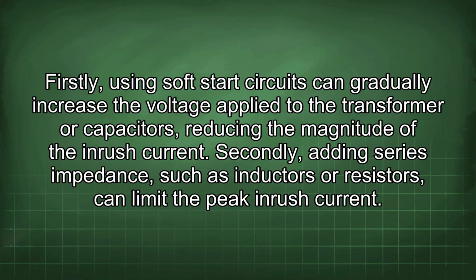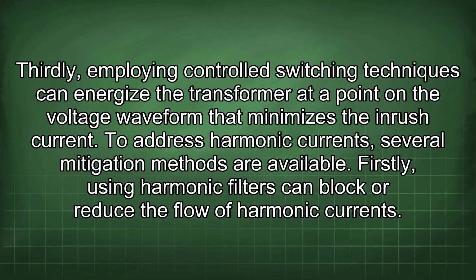Firstly, using soft-start circuits can gradually increase the voltage applied to the transformer or capacitors, reducing the magnitude of the inrush current. Secondly, adding series impedance such as inductors or resistors can limit the peak inrush current. Thirdly, employing controlled switching techniques can energize the transformer at a point in the voltage waveform that minimizes the inrush current. To address harmonic currents, several mitigation methods are available.